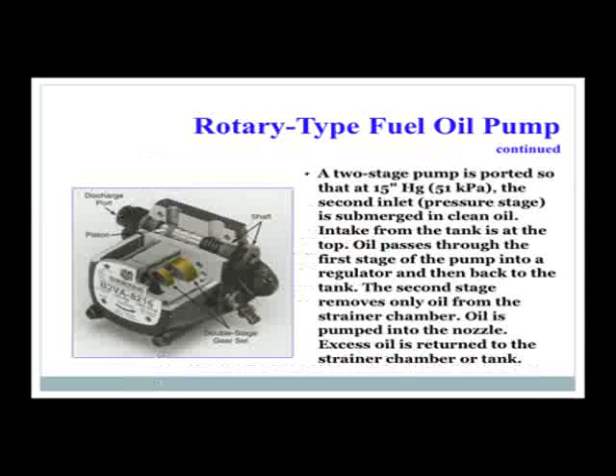The 2-stage pump is ported so that at 15 inches mercury, the second inlet is submerged in clean oil. Intake from the tank is at the top. Oil passes through the first stage of the pump and into the regulator, and then back to the tank. The second stage removes only oil from the strainer chamber. Oil is pumped into the nozzle. Excess oil is returned to the strainer chamber or tank.